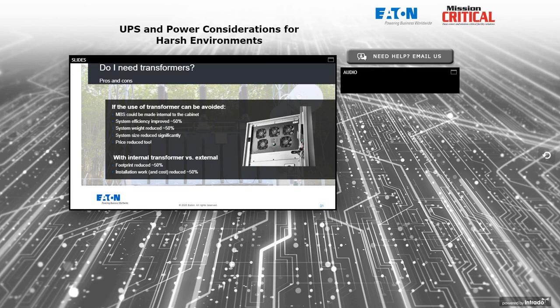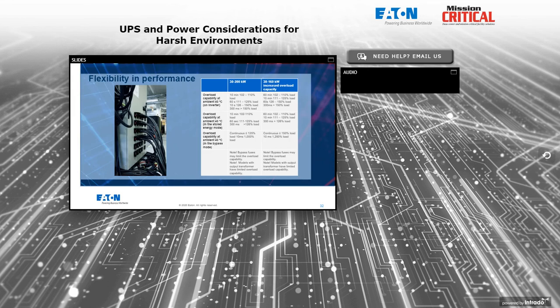But if I've got a specification that requires galvanic isolation, or if I need common mode noise isolation, for example, then a transformer is going to be required. And then I can always put a transformer next to the UPS in a commercial enclosure. But most of our clients would prefer to have the transformer, if it's associated with the UPS, be in a line-up and match cabinet or internal to the existing UPS cabinet. So we'll see some examples of that on the next slide, I believe.